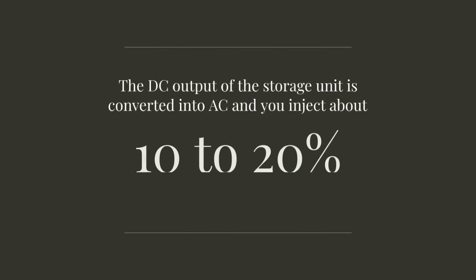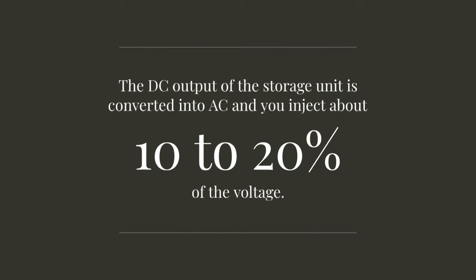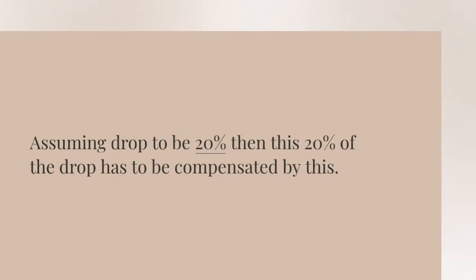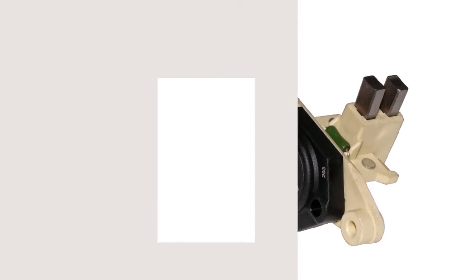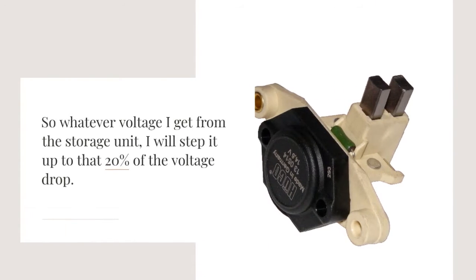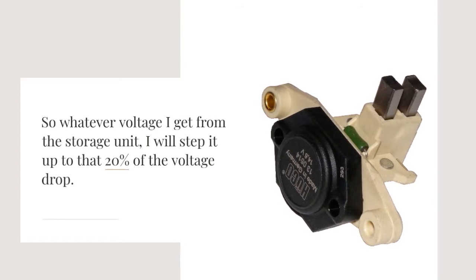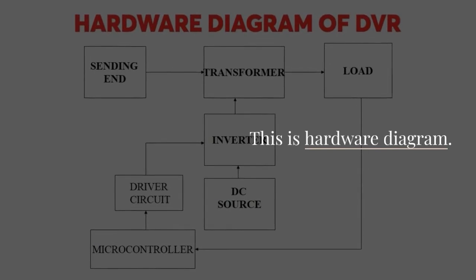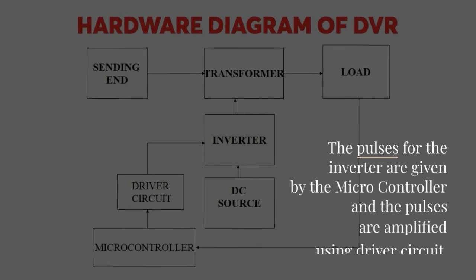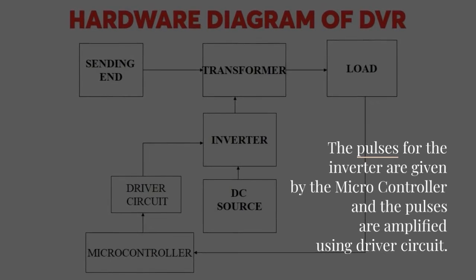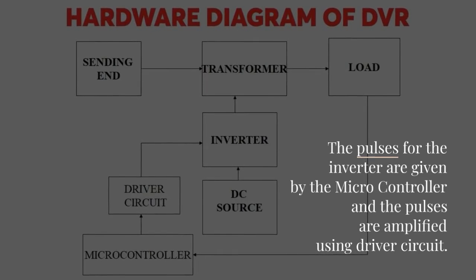The DC output of the storage unit is converted into AC and you inject about 10 to 20 percent of the voltage. Assuming drop to be 20 percent then this 20 percent of the drop has to be compensated. So whatever voltage I get from the storage unit I will step it up to that 20 percent of the voltage drop. This is hardware diagram. The pulses for the inverter are given by the microcontroller and the pulses are amplified using driver circuit.